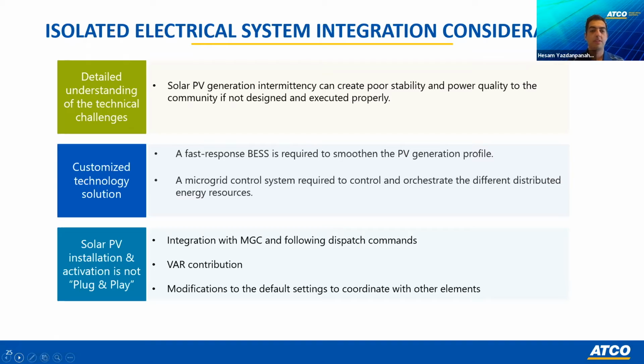The other difference is commissioning of the solar inverters is not plug and play like when you do it in Edmonton or Calgary. First off, you need to integrate them with microgrid controllers. You have to establish communication between them. The inverters need to send signals to the MGC and receive the dispatch signals from them. The other component is the inverters should contribute VAR support. Otherwise, if they continue working at unity power factor, the KVARs need to be supplied from the power plant, and it results in poor power factor in the gensets, which is not optimal operation for them.